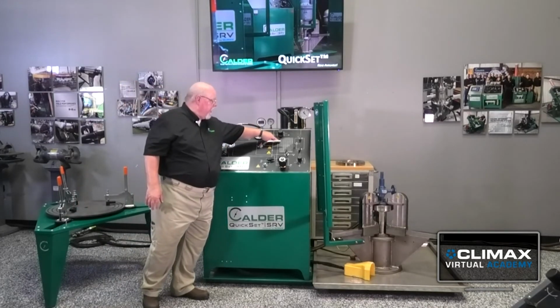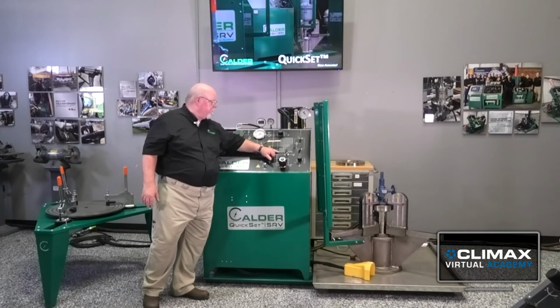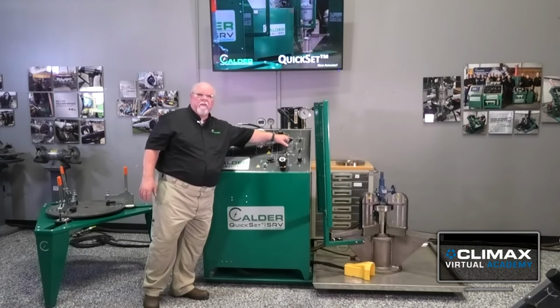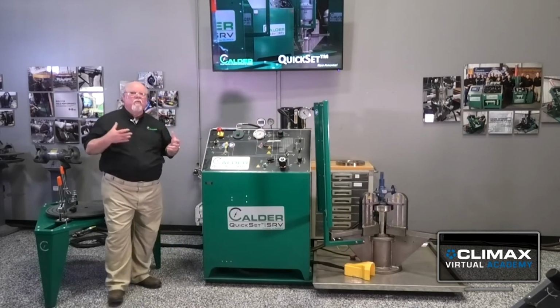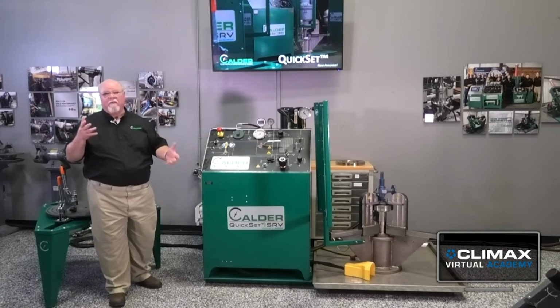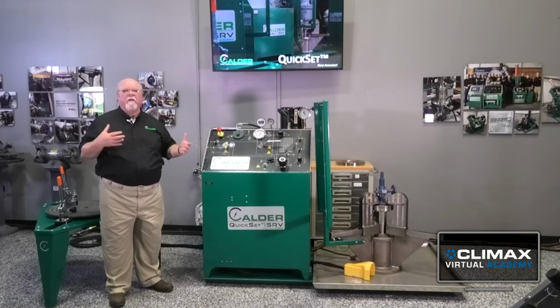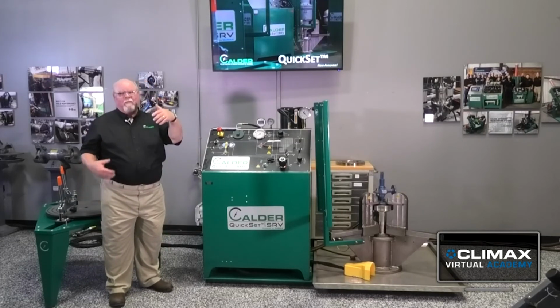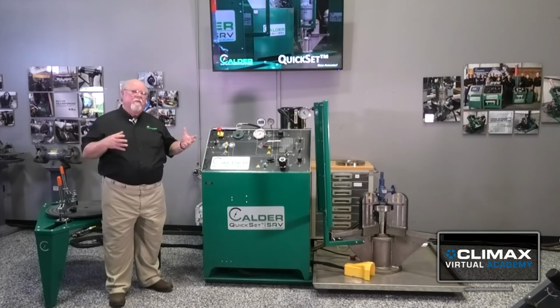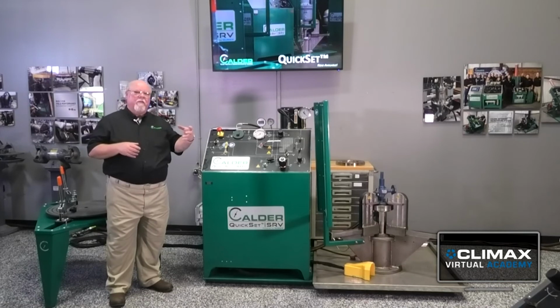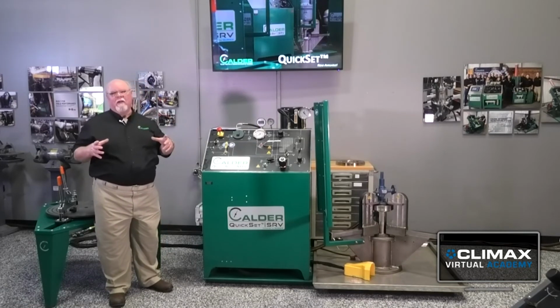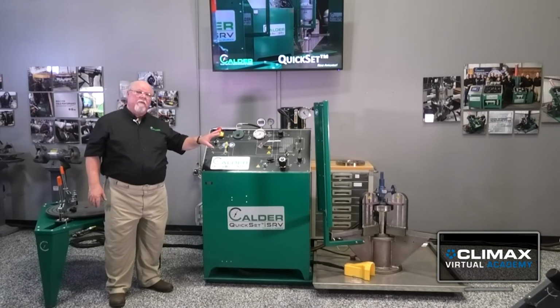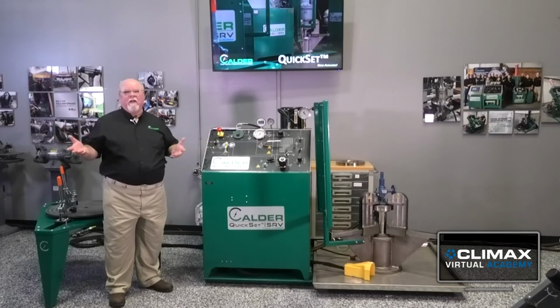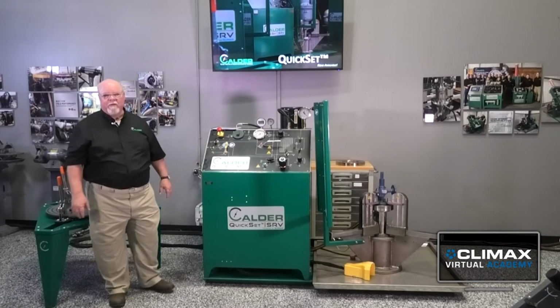When you look at the chart that we have here, we have the valve size along the rows, and the columns are set up for the test pressure. So it's going to come down to, if you have a 10-inch valve, is it a class 150, class 300, class 600? What is the range, and then what is the set pressure of the valve? A typical example is the moisture separator reheat valves. They're a 300 inlet flange, which could be up to 740 psi, but the set pressures are usually 400 psi and less. So the nameplate set pressure and the flange inlet size are going to dictate how much clamping force. We offer a range, from 30 to 60 tons, and we can cover a really broad range of valves with that range of clamping pressure. So good question.